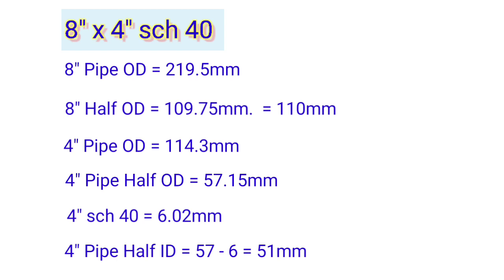4 inch pipe half OD is 57.15mm. As per schedule chart, 4 inch schedule 40 equals 6.02mm. So 4 inch half ID equals 57 minus 6, equals 51mm.